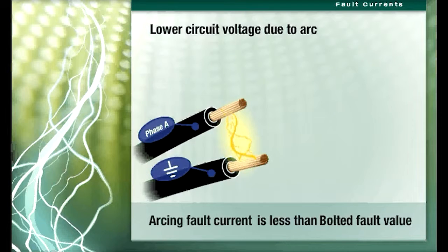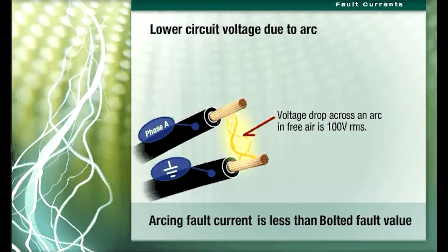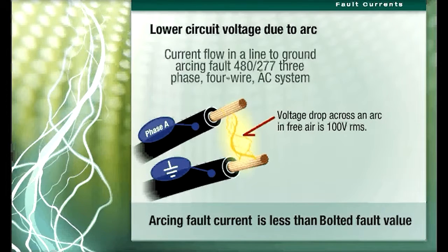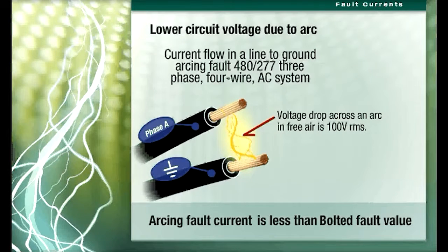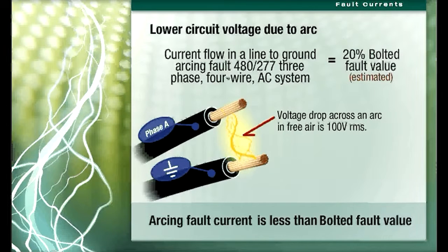The reduction is due to a lower voltage applied to the circuit due to the voltage drop across the arc. The voltage drop across an arc in free air is 100V RMS. Current flow in a line-to-ground arcing fault in a 480/277 three-phase four-wire AC system is estimated to be 20% of the bolted fault value.